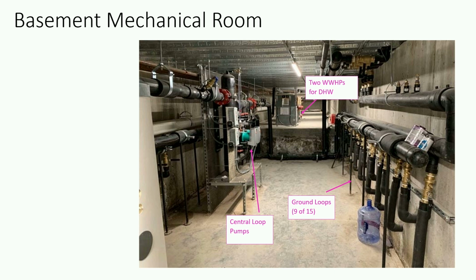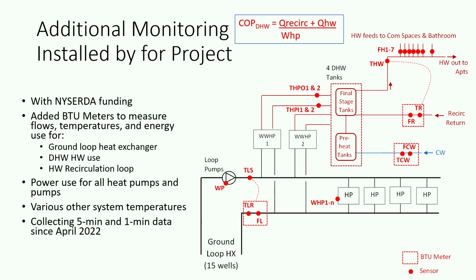And so, a geothermal system is really pretty boring in that there's nothing in the basement, right? You can see this is a picture of the ground loops coming into the basement, and then there's a pumping station in the middle, and up on the mezzanine in the back were two water-to-water heat pumps. And so this whole project had been funded by the NYSERDA new construction program. A lot of monitoring was already going in, and then the clean heat group at NYSERDA had funded me to add a few more meters and sensors to measure how the system works.